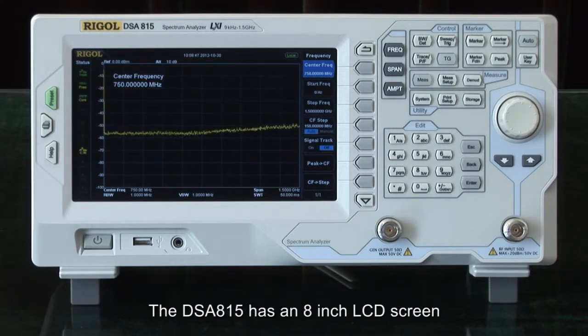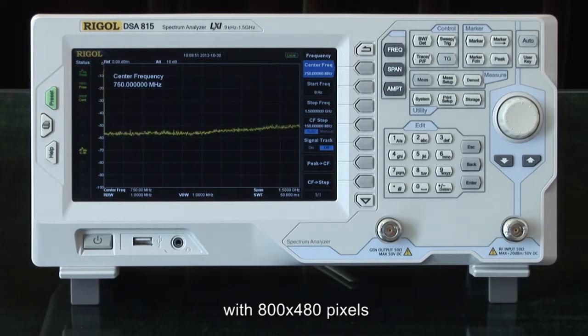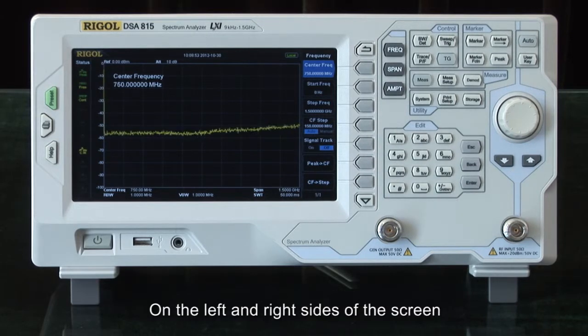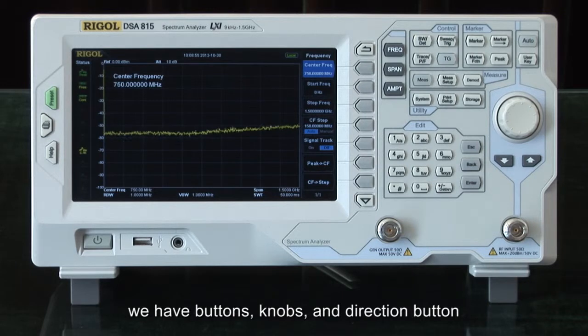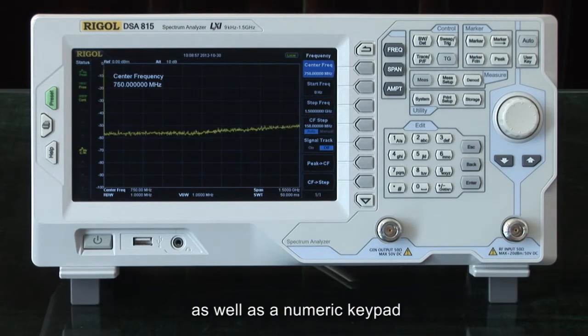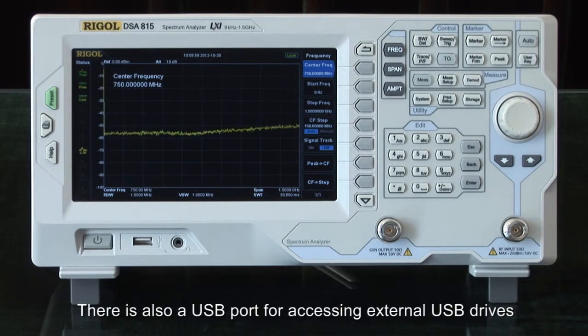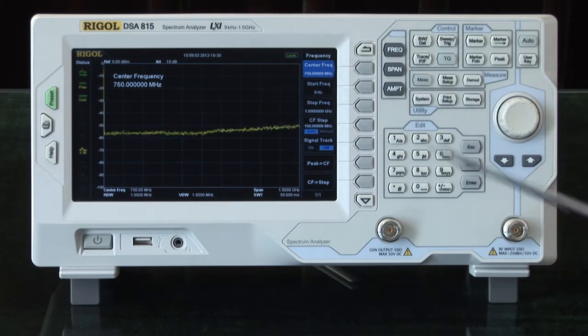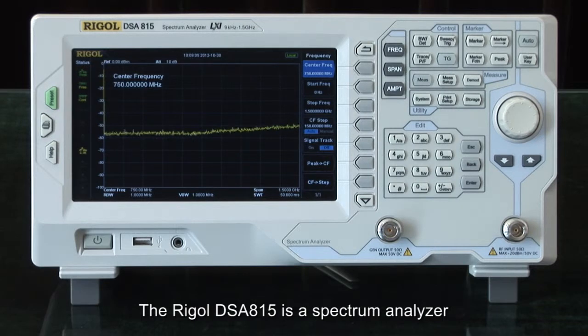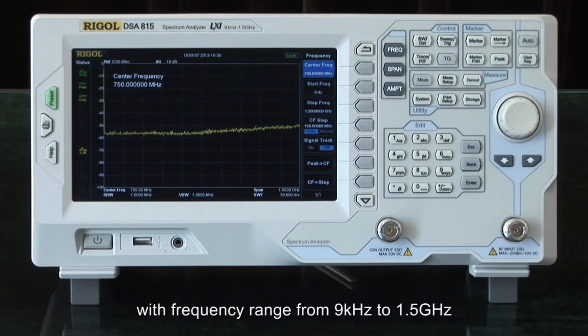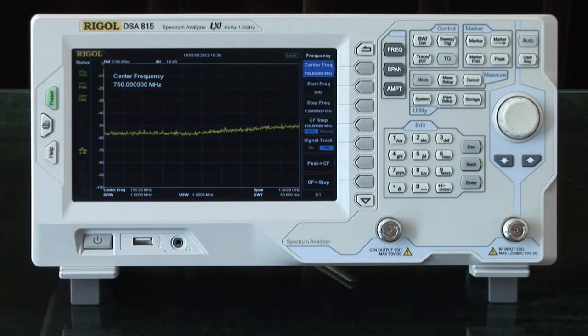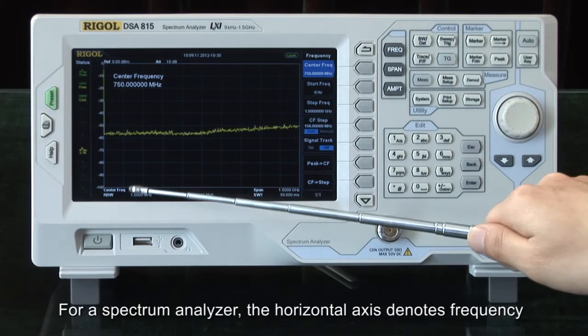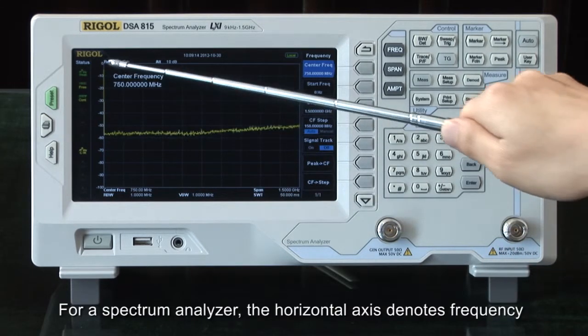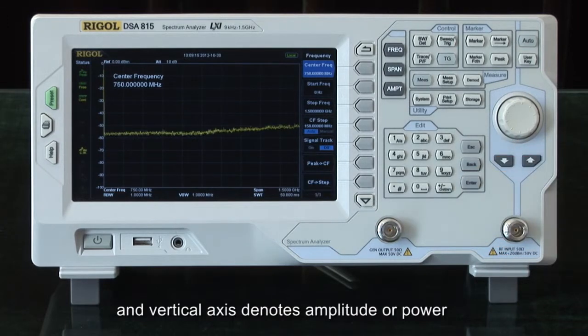The DSA-815 has an 8-inch LCD screen with 800 by 480 pixels. On the left and right sides of the screen, we have various buttons, knobs, and a direction button, as well as a numeric keypad. There is also a USB port for accessing external USB drives. The Rigol DSA-815 is a spectrum analyzer with frequency range from 9 kHz to 1.5 GHz. For a spectrum analyzer, the horizontal axis denotes frequency and vertical axis denotes amplitude or power.